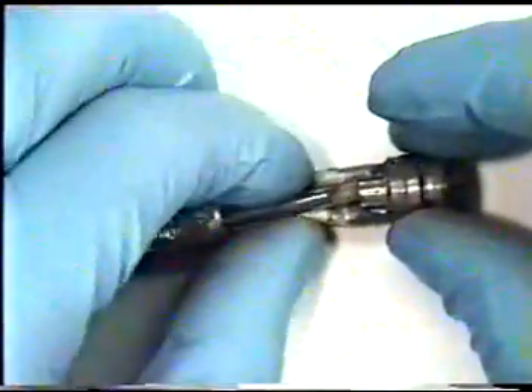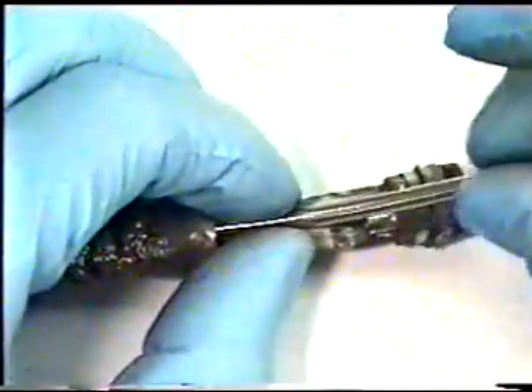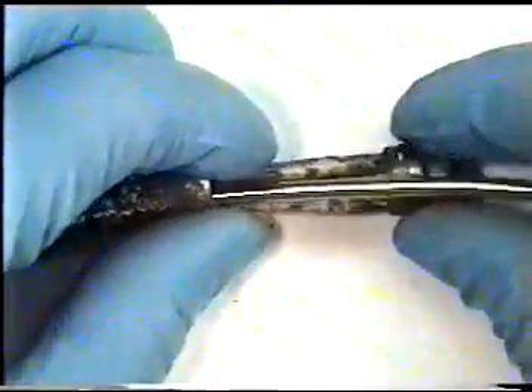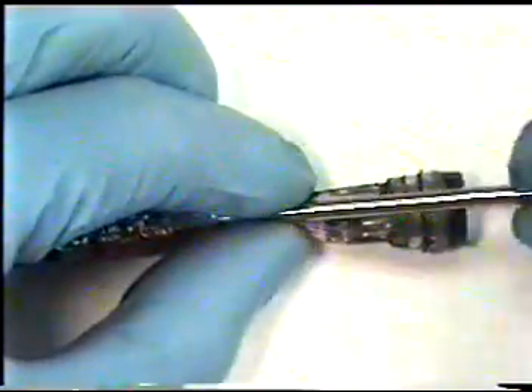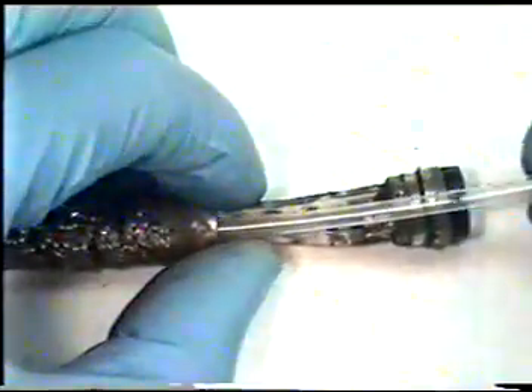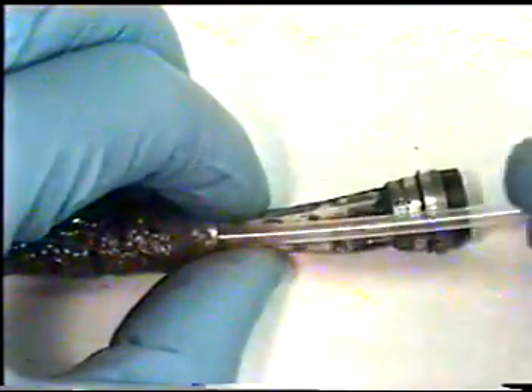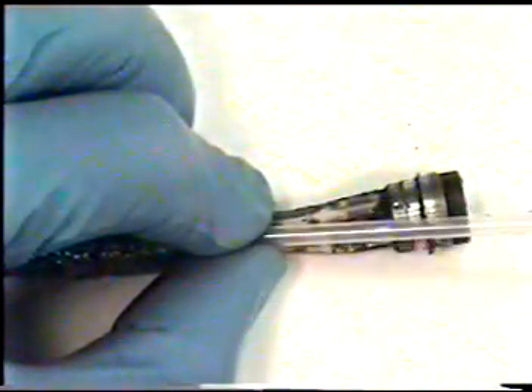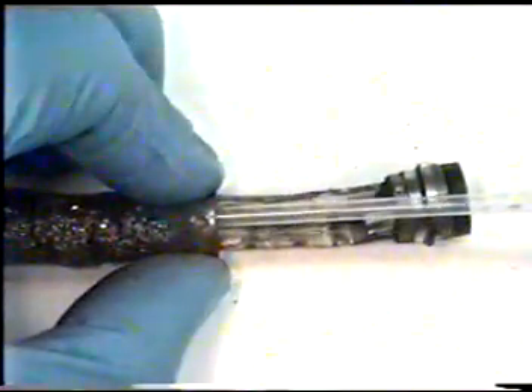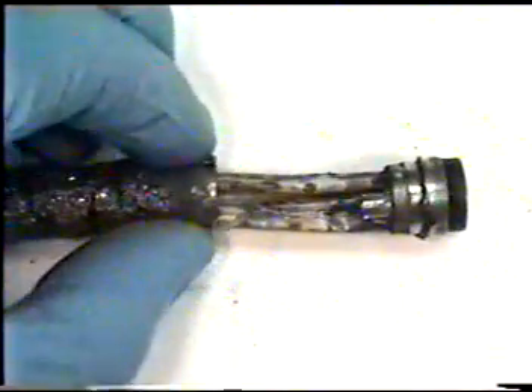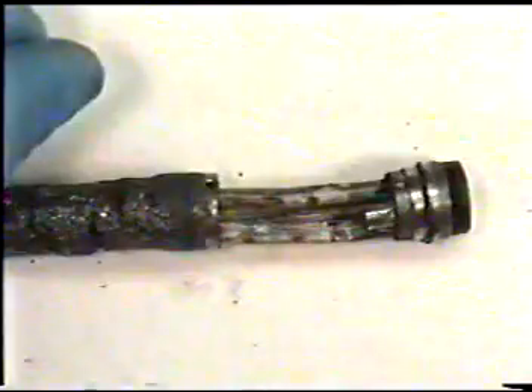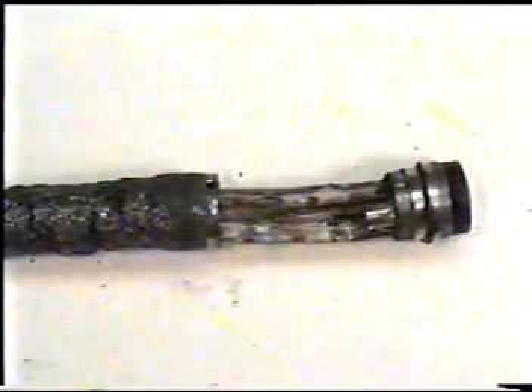Once you have carefully cut out your biopsy forceps channel from your distal end pipe, we will need to remove the biopsy channel completely so we can pull in our new light guide bundles without causing damage to them. Carefully slide out the entire biopsy channel through the insertion tube and remove completely. You will need to replace the biopsy channel with a brand new biopsy channel when we reassemble the endoscope.